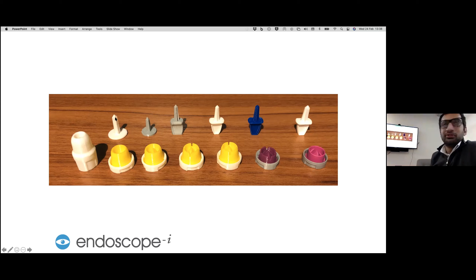So what about the trocar? Well, the trocar just had to do a pretty simple job. It needed to be sharp but blunt, so that, you know, we wanted to be able to stab through, but make sure that it didn't actually cause injury to someone. At the same time, it had to make sure it cleared the mask material inside the valve and wasn't obstructing it. Hence the reason we've created this crosshair effect, because when you twizzle it round, then it will clear some of that mask material.